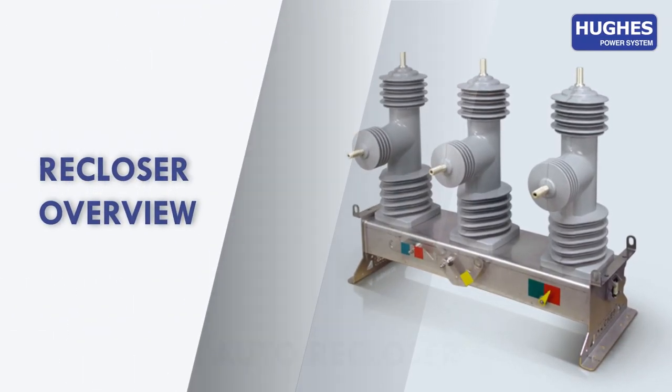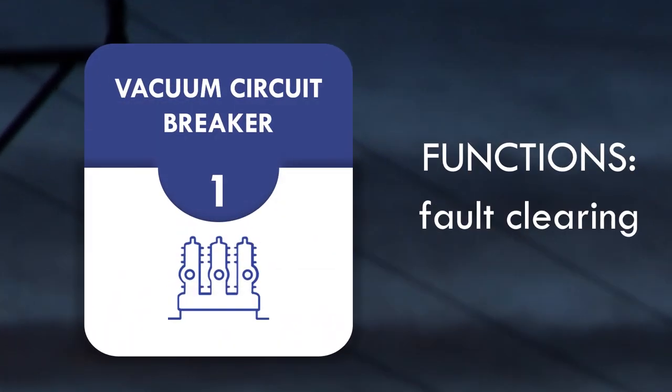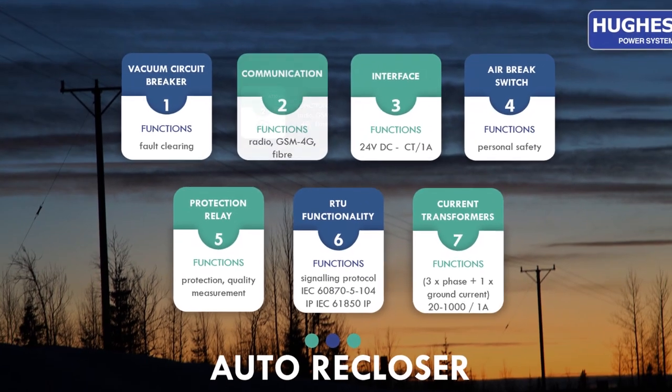Recloser Overview. Many customers are mistaken when defining a recloser. A recloser is a set of the following components: vacuum circuit breaker which has a function of fault clearance, communication which includes radio, GSM 4G, fiber, interface.